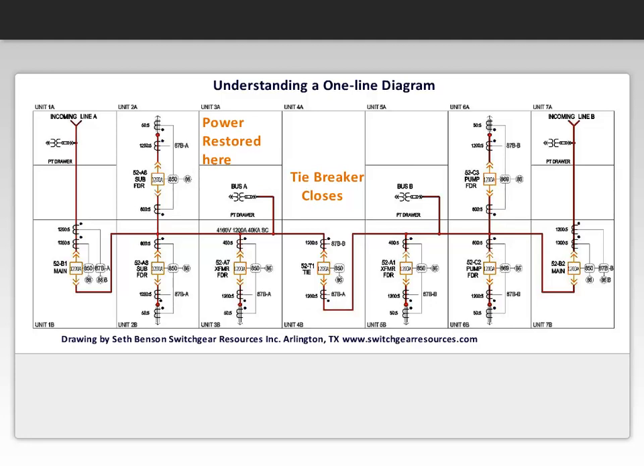A key interlock system such as provided by Kirk Key or Superior Lock is often employed. Typically, it involves opening the main breaker from the affected line, removing the key. The key is then inserted into the tiebreaker to allow it to close. Automatic transfer can occur by using a microprocessor PLC and having the necessary electrical and mechanical interlocks for the proper switchover to occur.